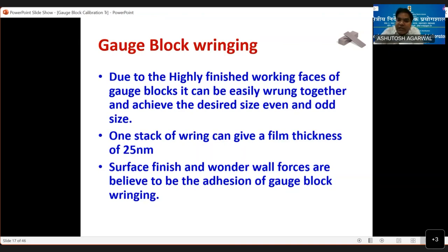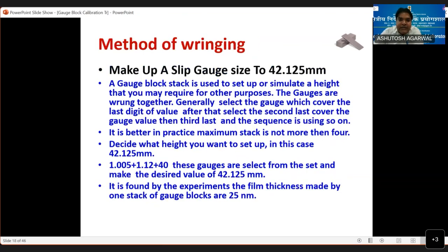One wringing joint can give a film thickness of 25 nanometers. So when you make the final dimension, you remove this 25 nanometers for each joint. So if you use 7 blocks, remove 6, 6 multiplied by 25. Surface finish and van der Waals forces are believed to be the cause of the gauge blocks sticking in wringing. So this is the reason why they stick.